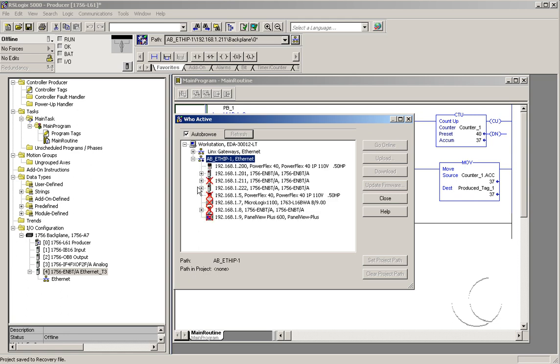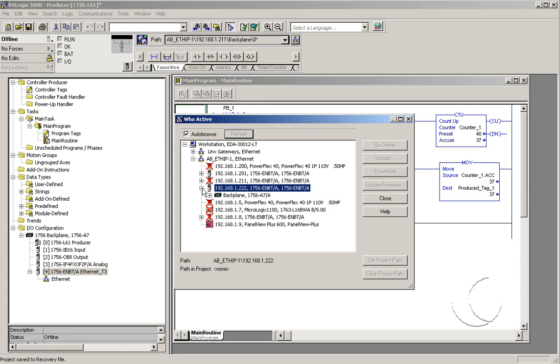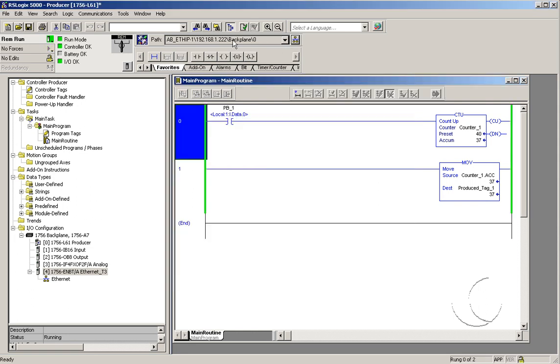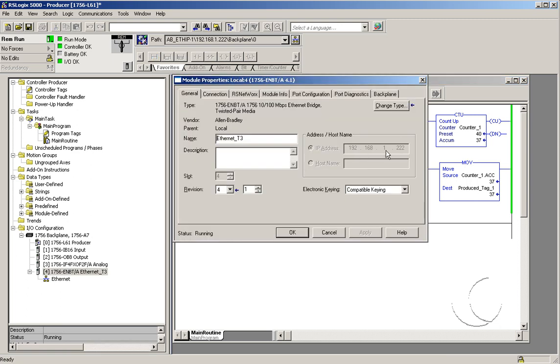You can see it's browsing. When I expand it again, you can see that it's now showing the new IP address that I just configured on the system. The other devices that are no longer accessible because they've been disconnected get a red X. I have this processor, which is a different unit, and then I have the one I've just been working with and changed the IP address on. In order to connect to it, click the plus sign, click the plus sign on the backplane, click the processor. Now the options are available on the right, and I want to go online with this unit. It's also good practice to set the project path now that you have defined the new connection, then go online — this will save and update the project path. You can see we are online. Verify the IP settings — it's showing .222. We are good to go.